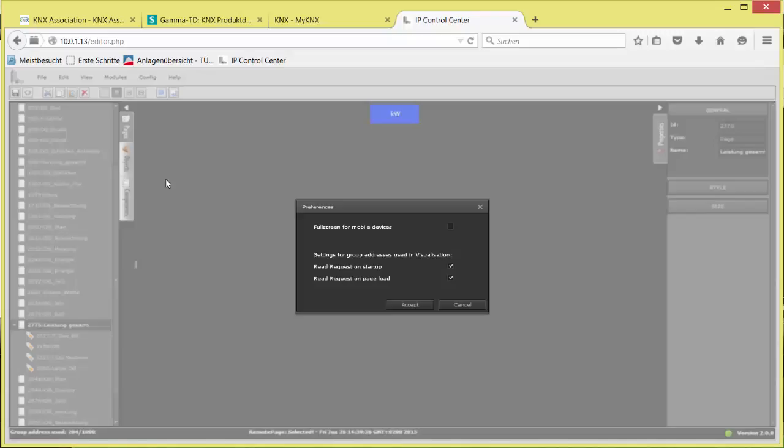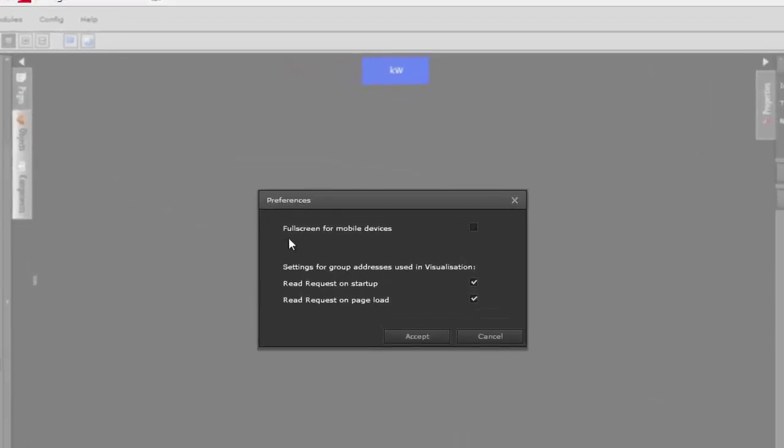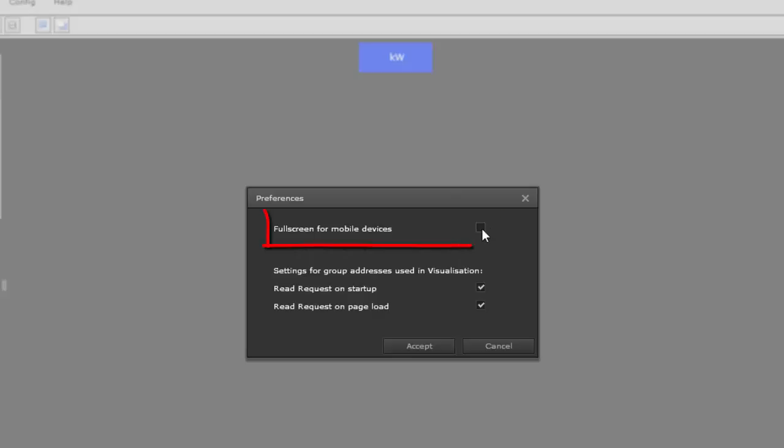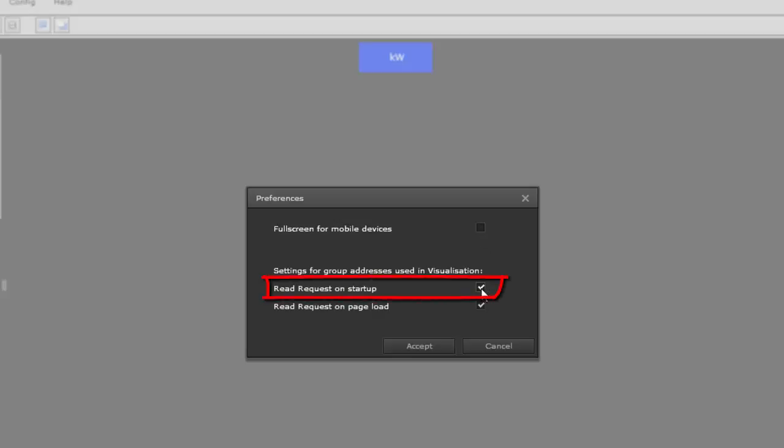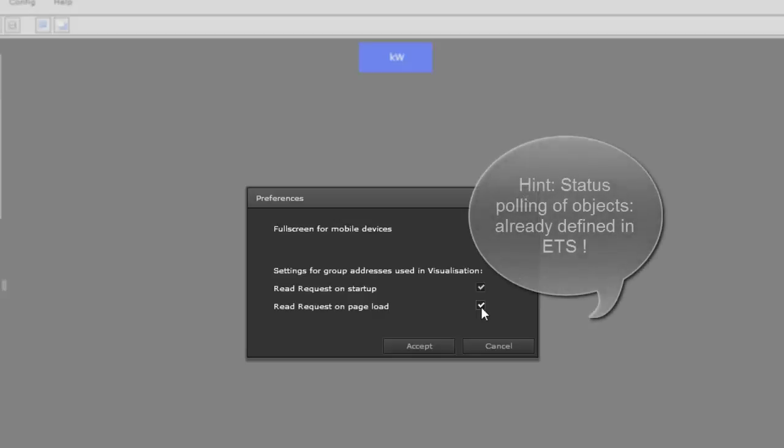Preferences. Full screen for mobile devices provides a flexible zoom with full screen display on smartphones. If this option is not used, the original page resolution will be used, which can result in poor display quality. Read requests for all state group addresses can be launched after a device reset as well as with a page change per each new open page if ticked. The startup status polling of the 250 possible communication objects, however, is set already and only in ETS.